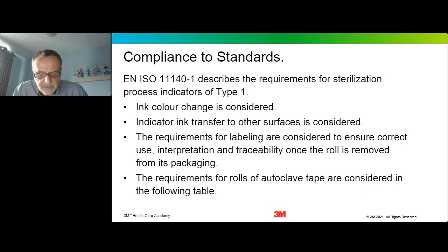Now, if we look at the specific requirements for type 1 process chemical indicators, and this is what these types of indicator are that are printed on the surface of autoclave tape, they are type 1 process indicators according to the definitions in EN ISO 11140. Then this document covers 4 main areas. The first is the nature of the colour change for the indicator ink printed on the tape. The second relates to the transfer of the ink to other surfaces which may come into contact with the ink. And as you can imagine, packs will often touch each other both before, during and after sterilisation, and there must be limits on the transfer of ink from the autoclave tape onto other surfaces which it might touch. The third relates to the labelling and support material which should be supplied with the tape.